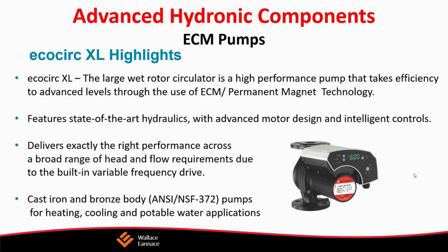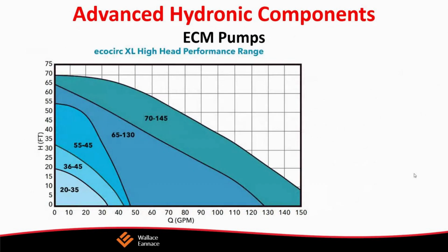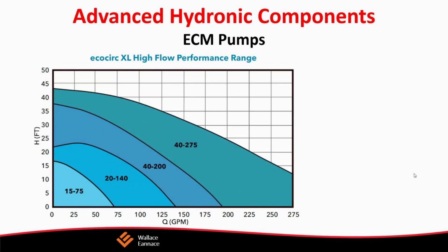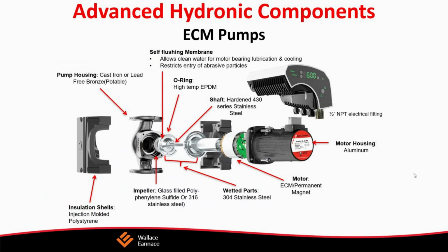Bell & Gossett makes an outstanding line of large wet rotor pumps called the EcoCirc XL. These pumps also feature ECM motors. There are 13 models that go up to 275 GPM. They also have 4 control modes: proportional pressure, constant speed, and it has also automatic night mode. Comes standard with BMS communication, Modbus, and BACnet, and can also communicate with a laptop.